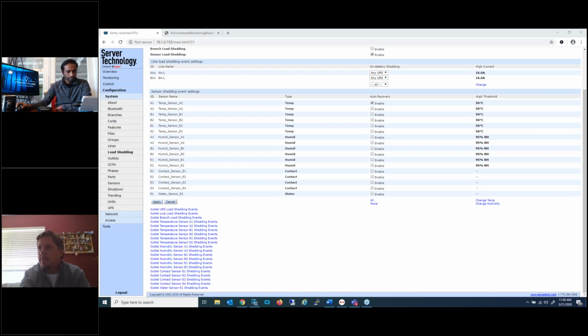And I should mention that for those of you that might not be using our Pro Series PDUs, which began to enter the marketplace in very early 2015, if you're using our older CDU Series PDUs, they supported load shedding as well. It was always a key activated feature, and still is, but if you have the older cabinet distribution unit series, not the Pro Series, we can provide you an activation key to enable that feature, and that would be provided at no charge. With the Pro Series, simply keeping your firmware up to date, getting to 8.0p and later, automatically enables the feature for you. All right.